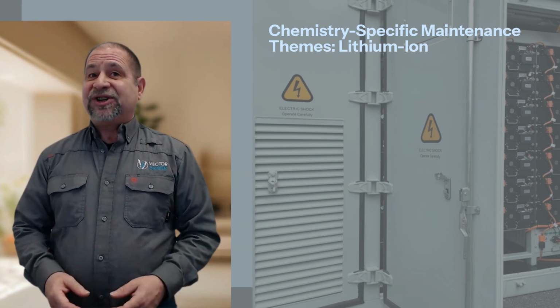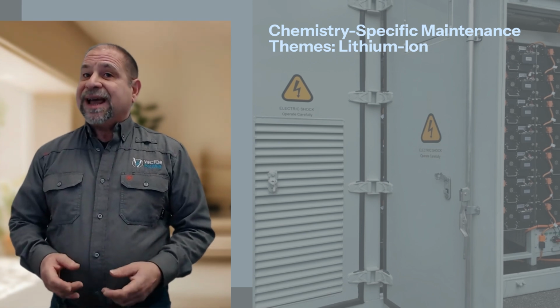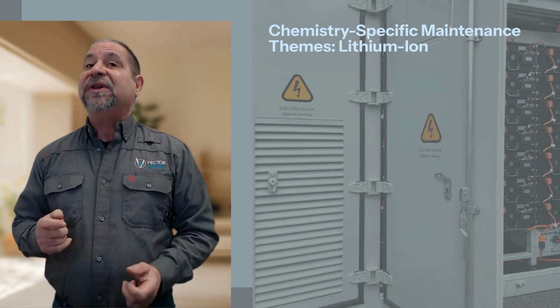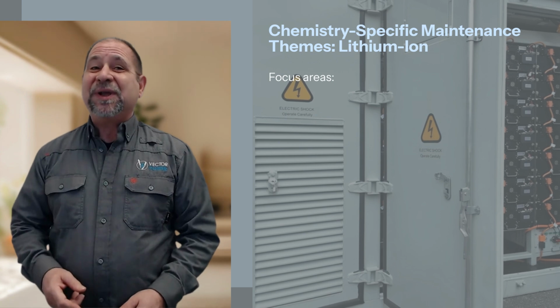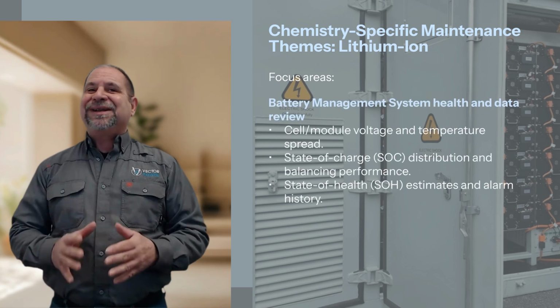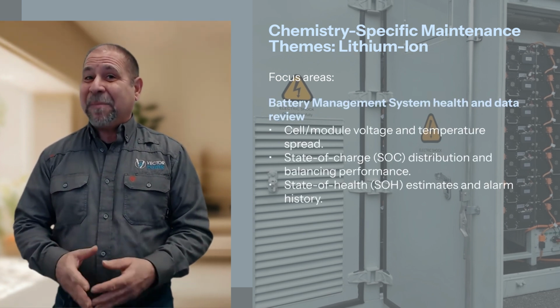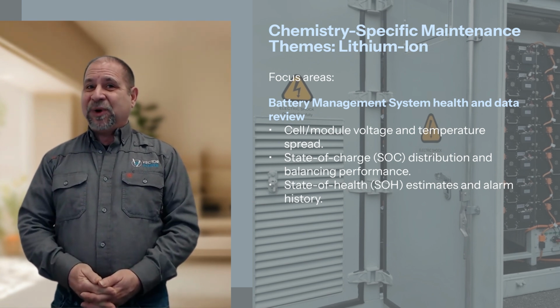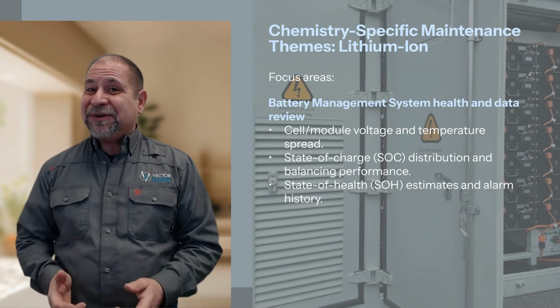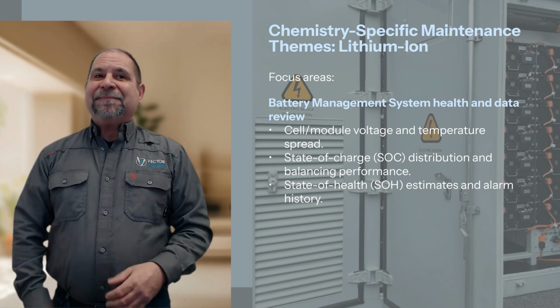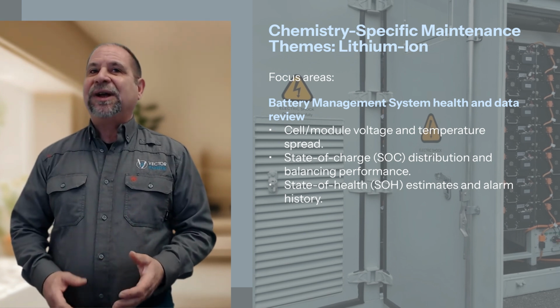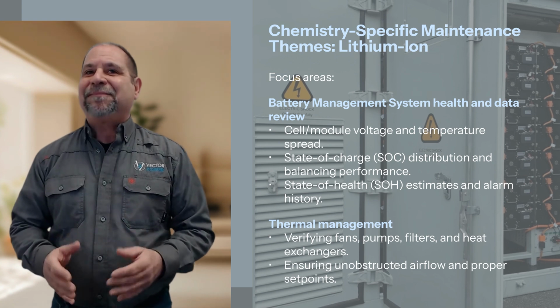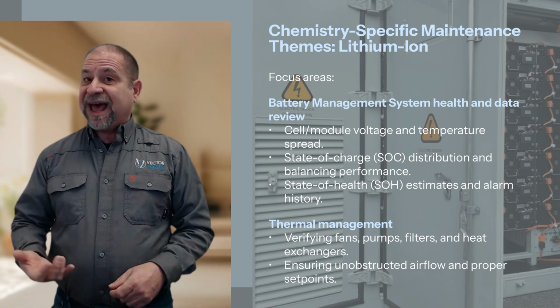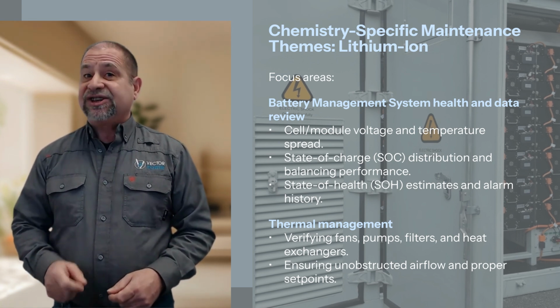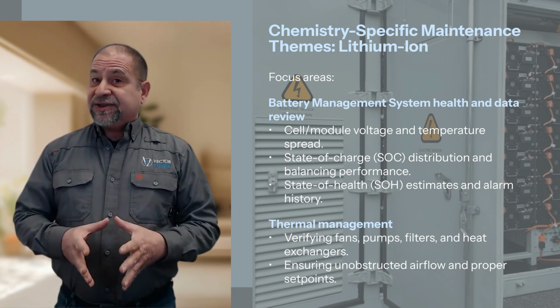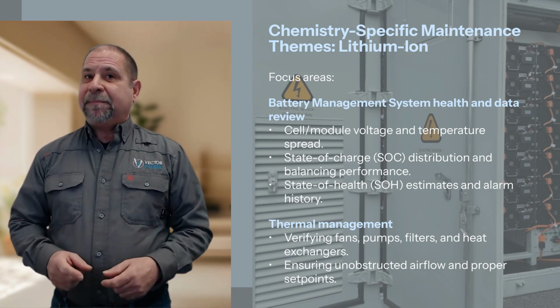Lithium-ion battery energy storage systems rely more on electronic and control integrity than on hands-on work within the battery modules. Important focus areas include battery management system health and data review. Monitor cell and module voltage and temperature spread, review state of charge distribution and balancing performance, check state of health estimates and alarm history. Thermal management focus. This involves verifying fans, pumps, filters, and heat exchangers, and ensuring unobstructed airflow and proper set points.